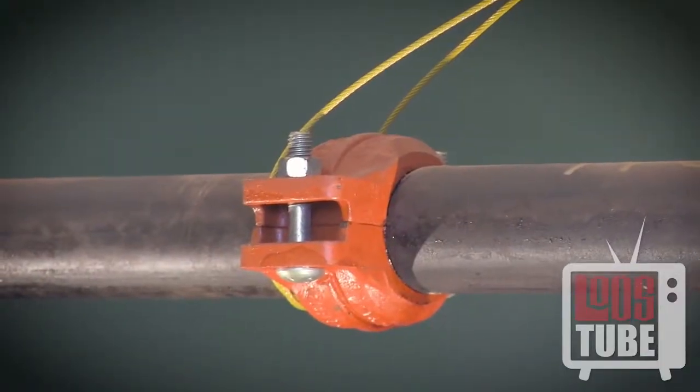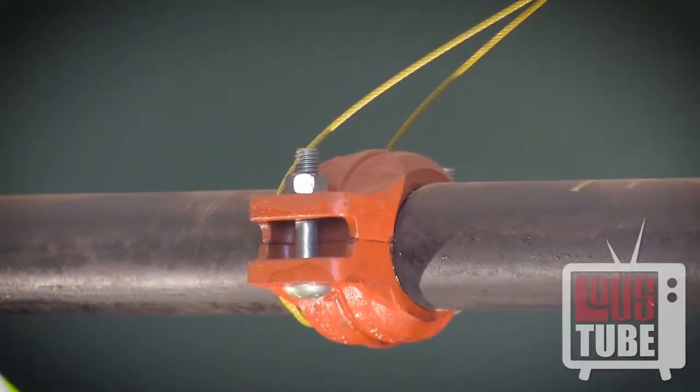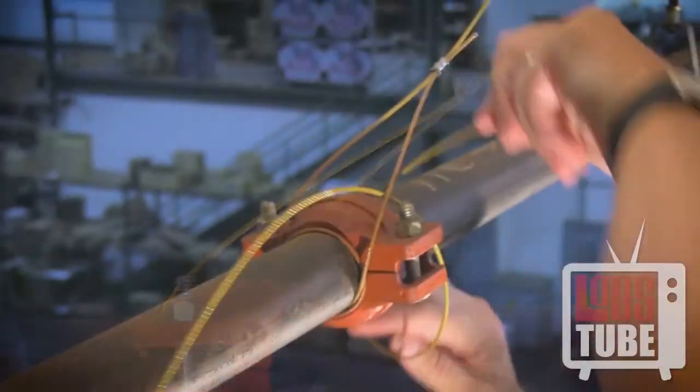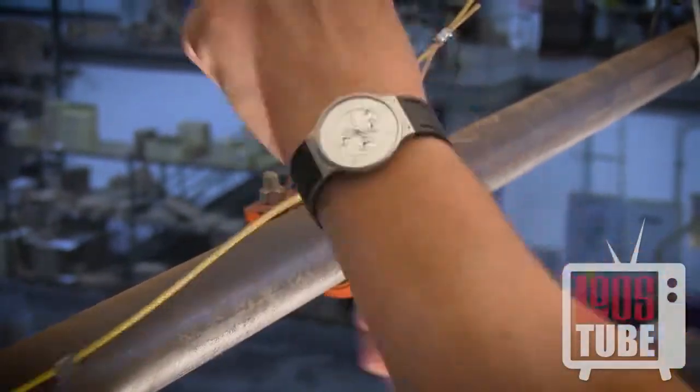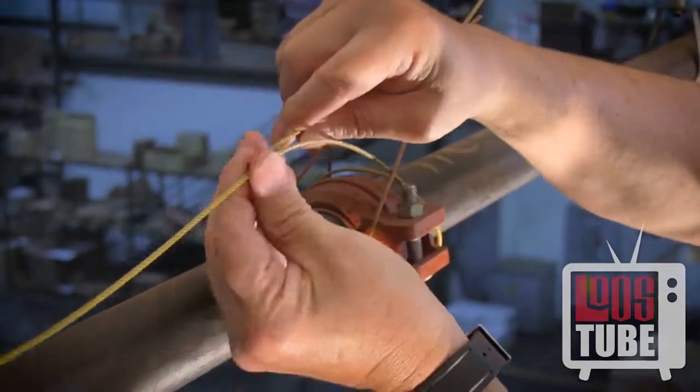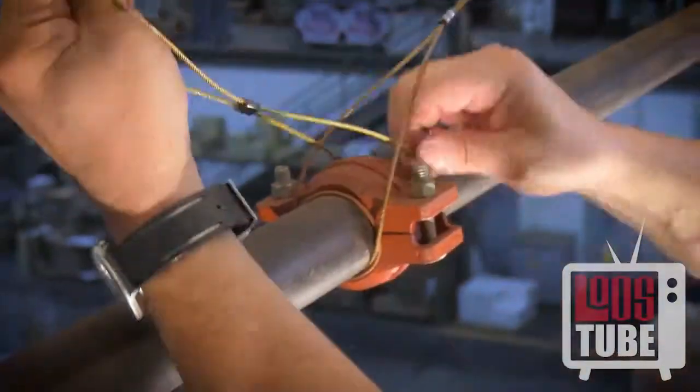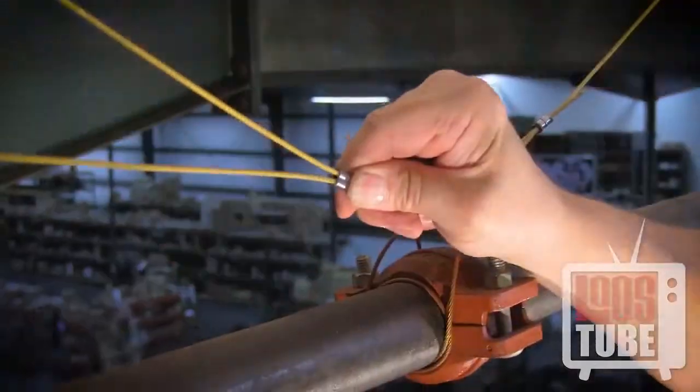Cable sway bracing works in tension only, which means that two braces must always be applied opposing each other. Repeat this process in the same manner in the opposite direction, ensuring that the cable is looped around the opposite side of the coupling or clamp.